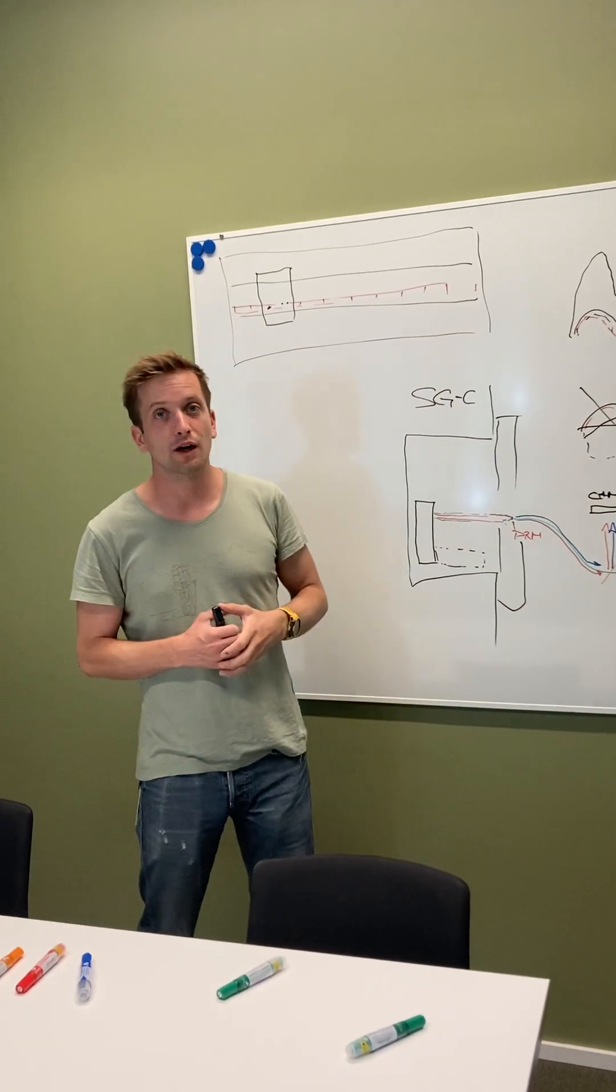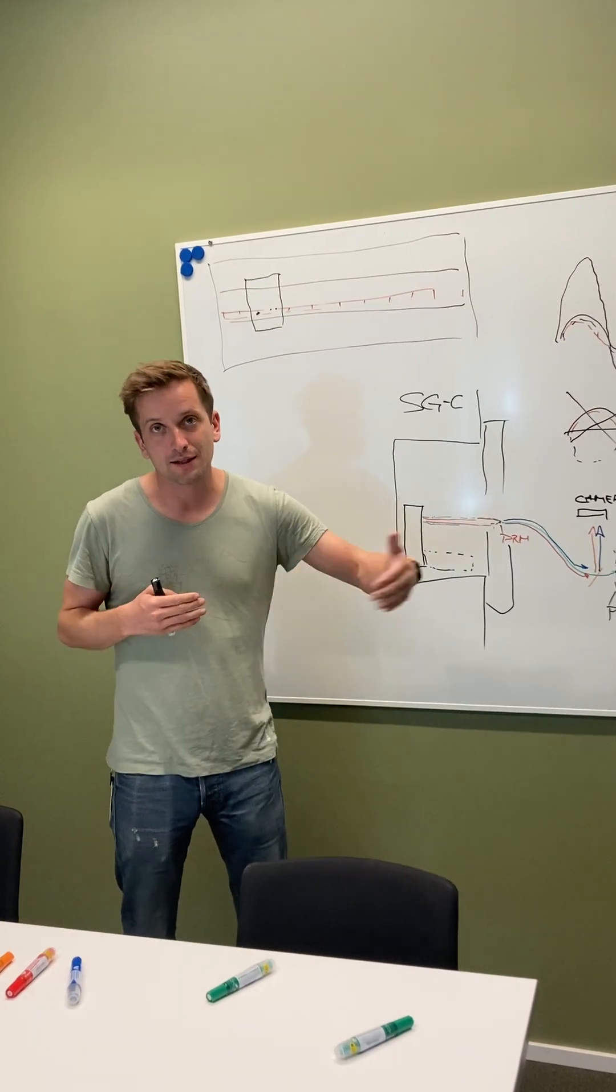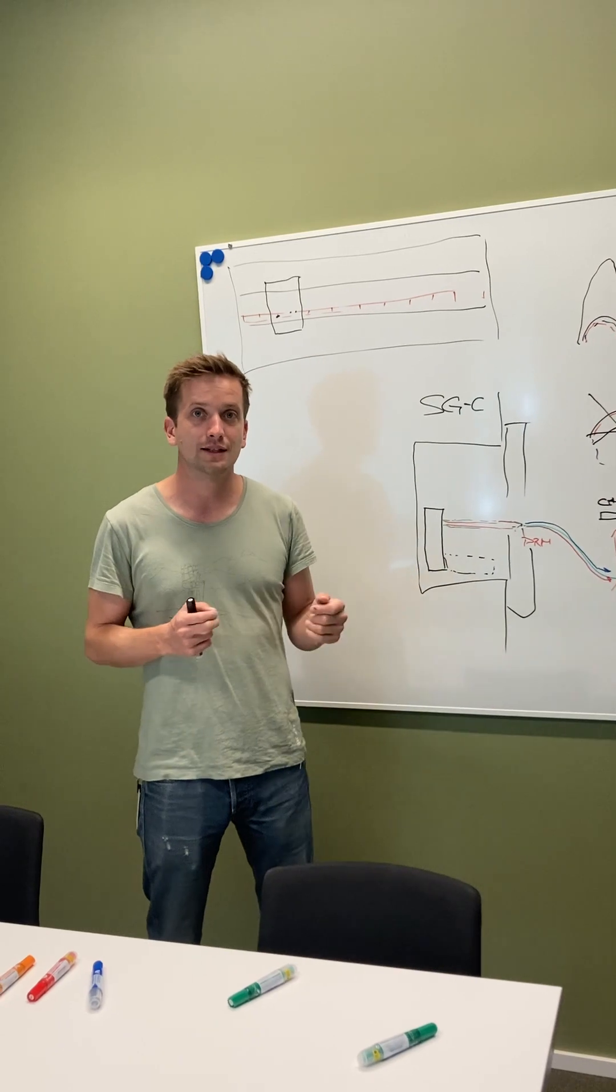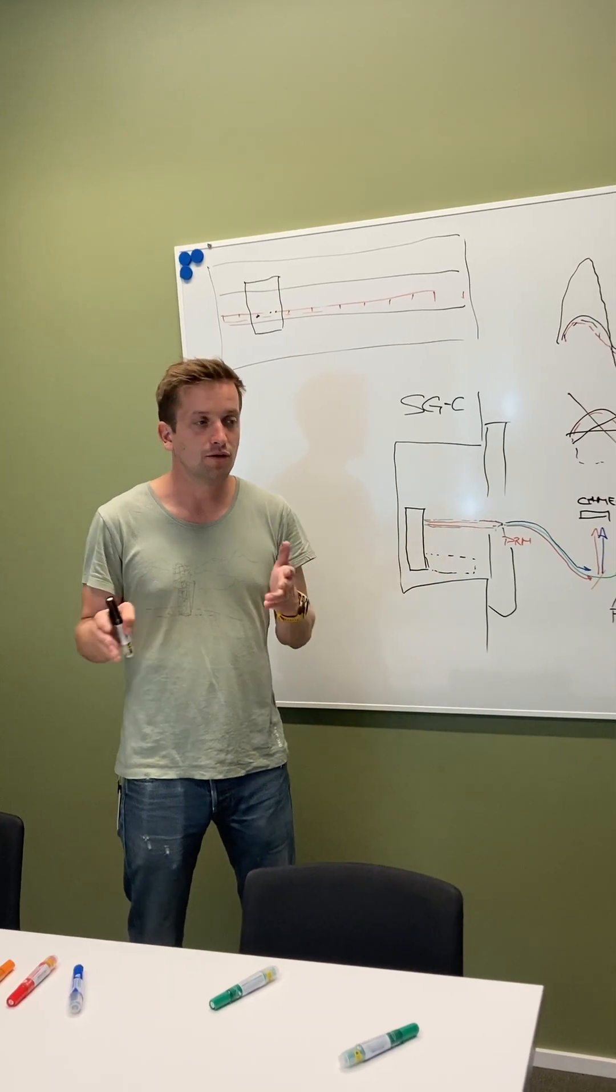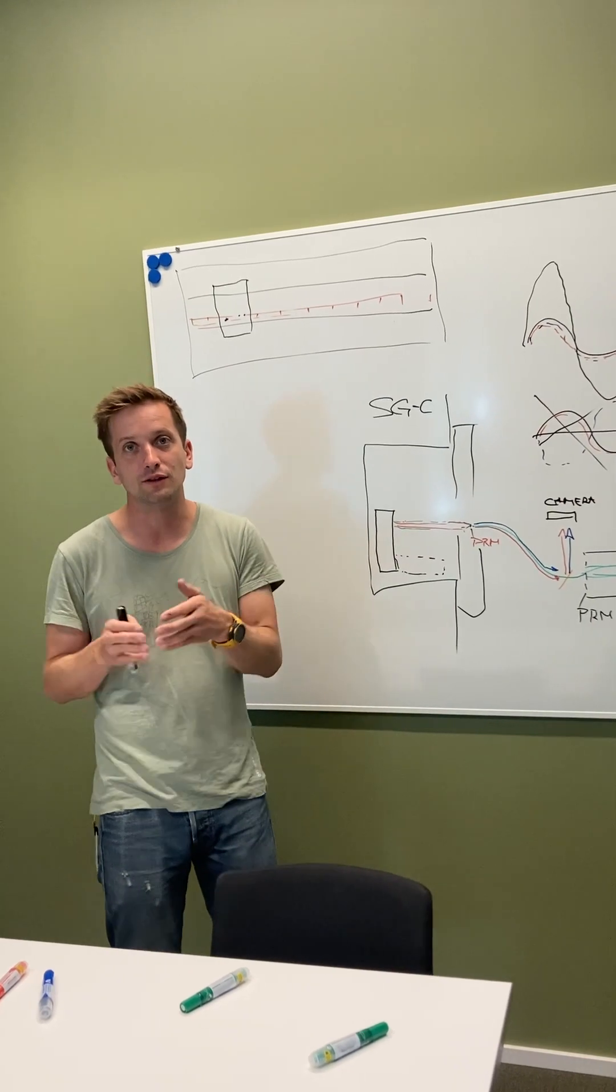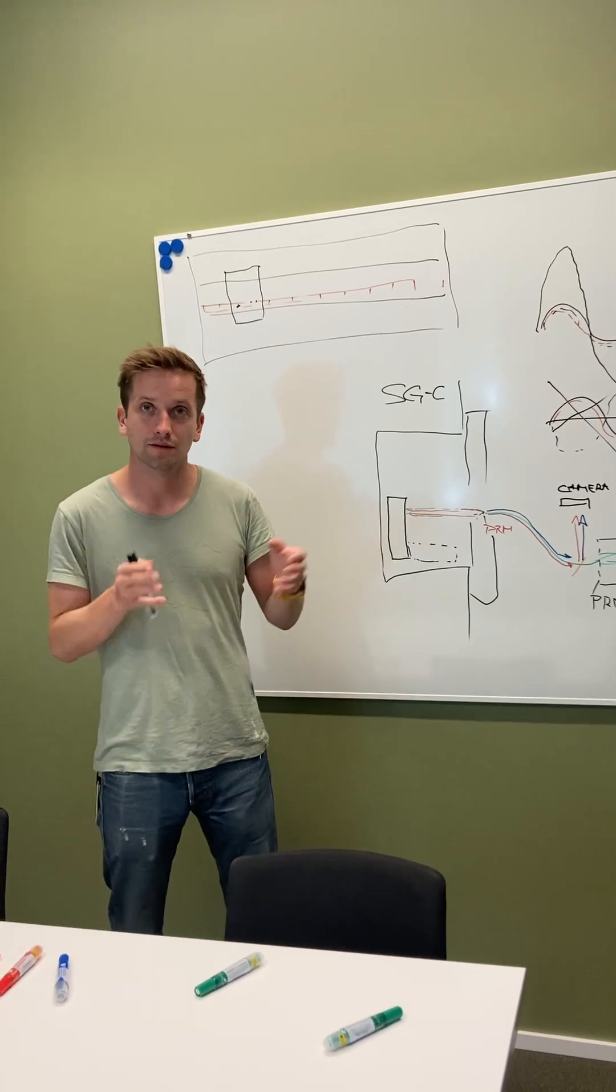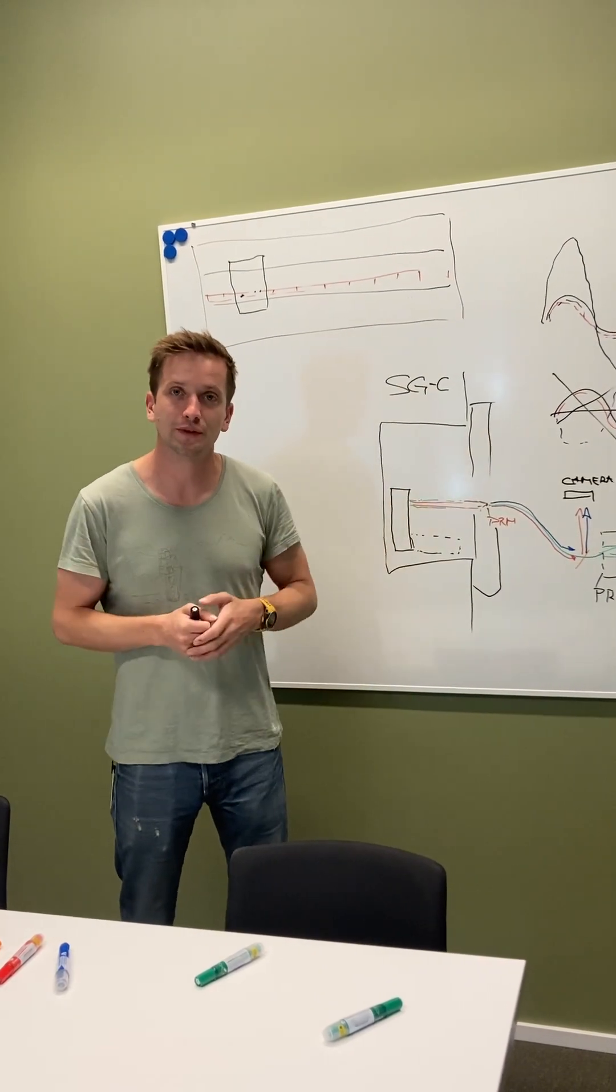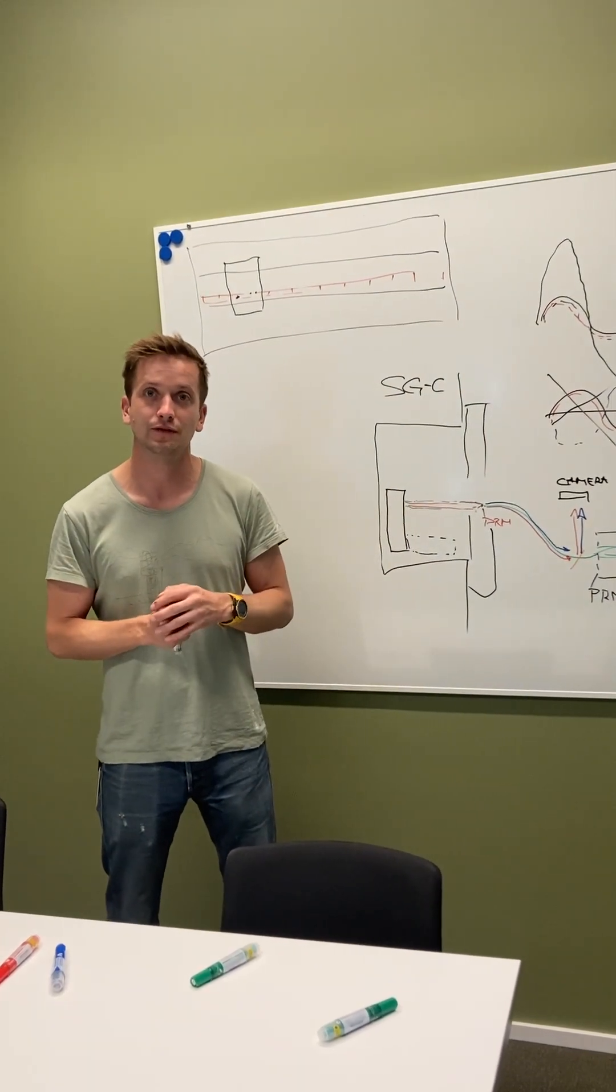With the absolute interferometer, however, you have to make a scan of wavelengths for each measurement, and that's then fairly slow. That's in the range of half a second to two seconds per measurement that you need to invest. So there is also a scope, a different kind of scope that you can achieve with an absolute interferometer.